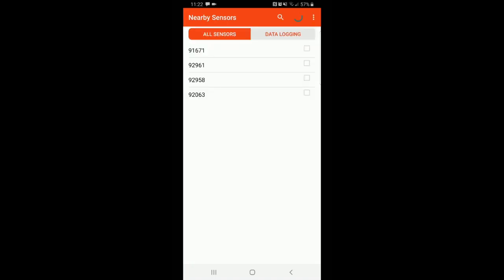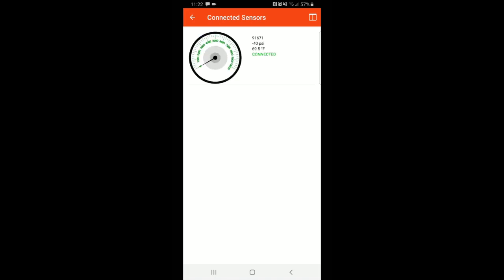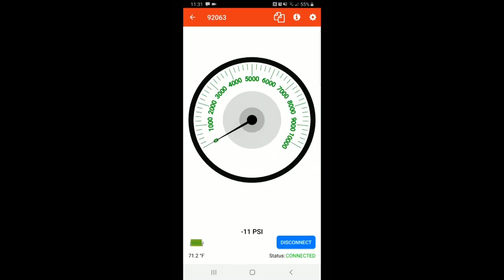To select a transducer, you simply click the one that you are attempting to utilize, and then click on the connect icon that appears at the top of the app. When it opens, it will show that it is connected, the transducer in question, the relative pressure that it is showing, as well as ambient air temperature. You can simply click on the picture of the gauge itself, and this will cause it to go to full screen mode. As you can see here, it is currently displayed as negative 11 psi.